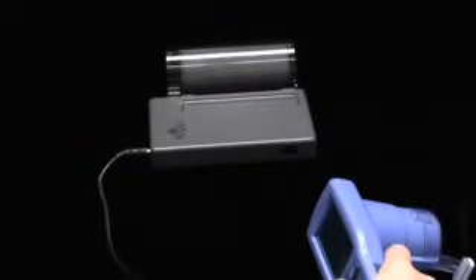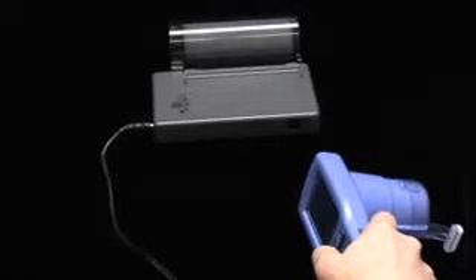Point the infrared window of the pupillometer about 6 inches away from the printer and then press the select key. The pupillometer must be within range of the printer, pointed directly at the infrared window of the printer, and the printer must be turned on.